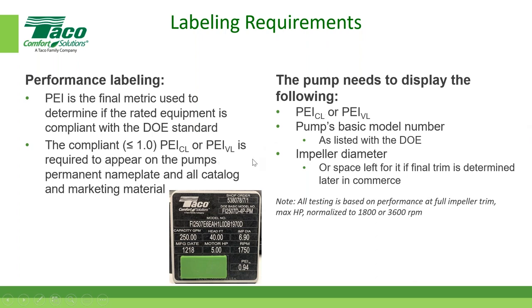Moving on. So please be advised that TACO pumps meet the DOE requirements. Personally, I think we exceed them better than most, and we could get into another whole discussion about that, but that's not what this presentation is about. On the pump tag, and this is important for all you folks, not just for TACO, all pump manufacturers now need to have this information right here: the PEI number, which is the pump energy index, the rating the Department of Energy came up with, and the actual DOE basic model number. That information has to be on there, as well as the documentation associated with the pump.